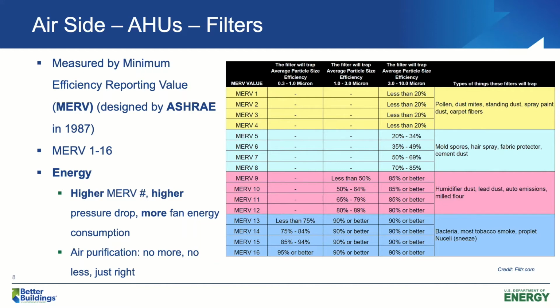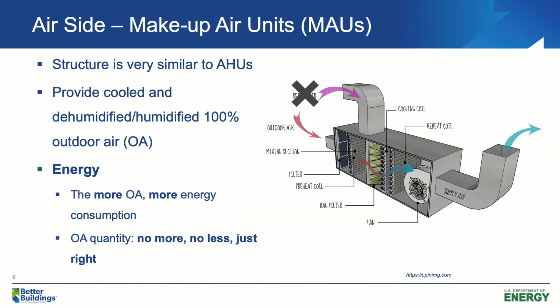We definitely do not want to under-purify the air because it might compromise the quality of our products. But on the other hand, we do not want to over-purify the air either because that means energy penalty. No more, no less, just right. Makeup air units. Makeup air units are very similar to air handling units. The only difference between these 2 types of equipment is that makeup air units do not take any return air from the spaces. All the air comes from outside. Essentially, they are 100% outdoor air handling units.